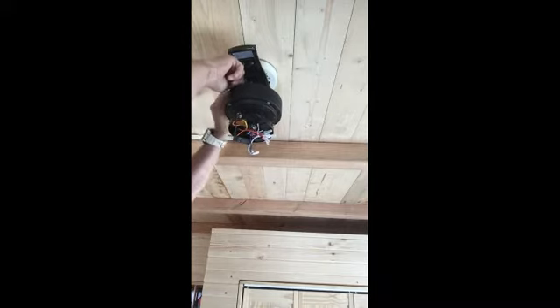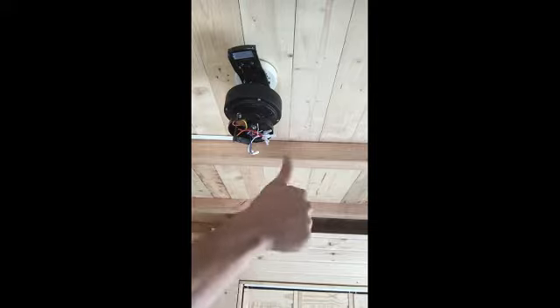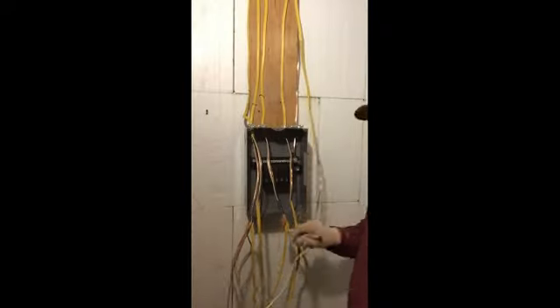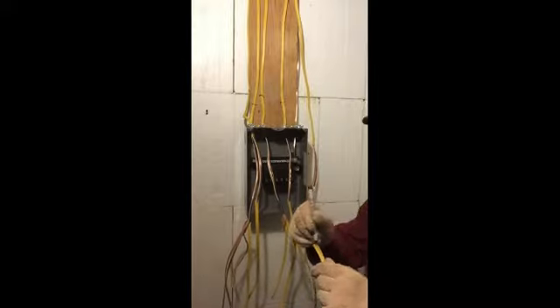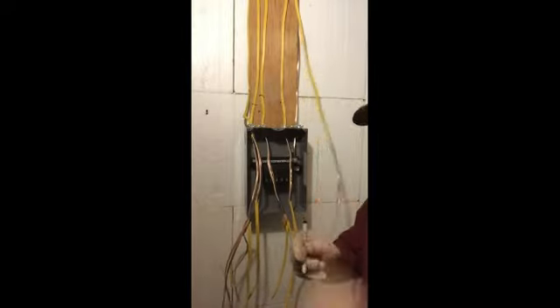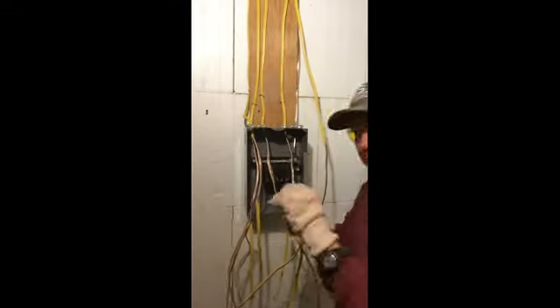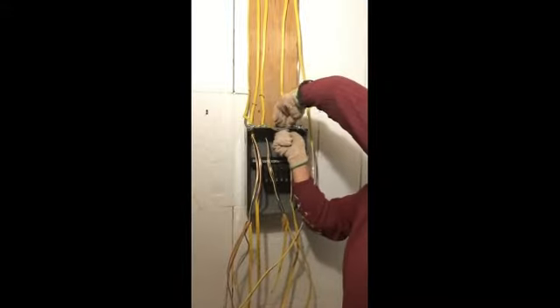Now, a couple of things here. When running feeds from your panel box, I would use a black magic marker and label each of the wires that go in, so you understand it's outside, it's your range, it's the kitchen, it's bedroom number 1, things like that. It's your jet pump for the well. That way, when you go back through, you're going to have to label your panel box when all your circuit breakers are installed, and it makes life a lot easier.